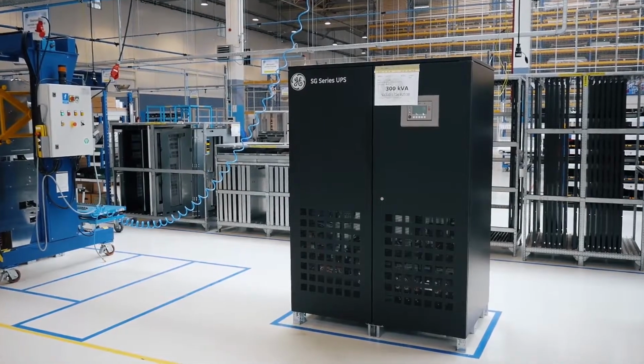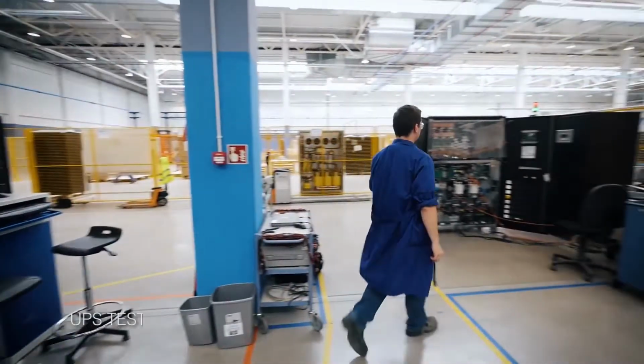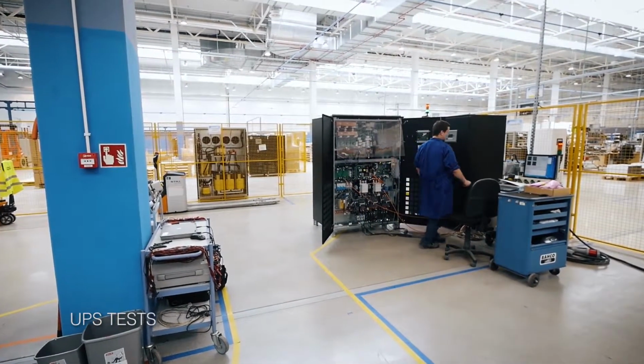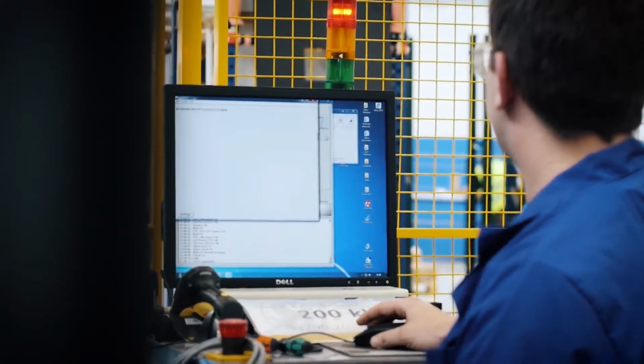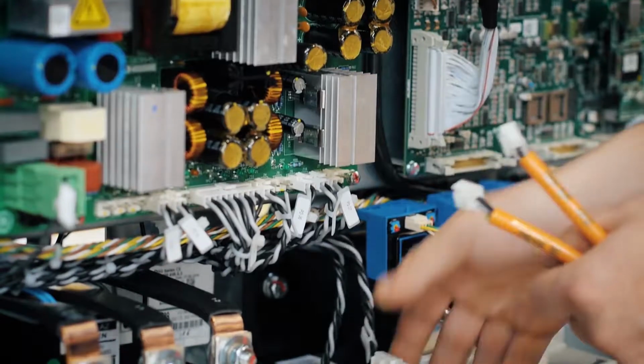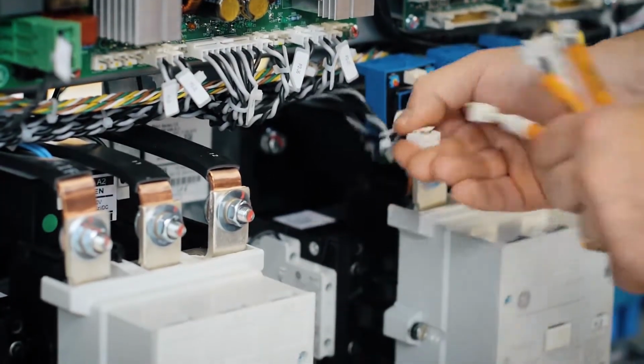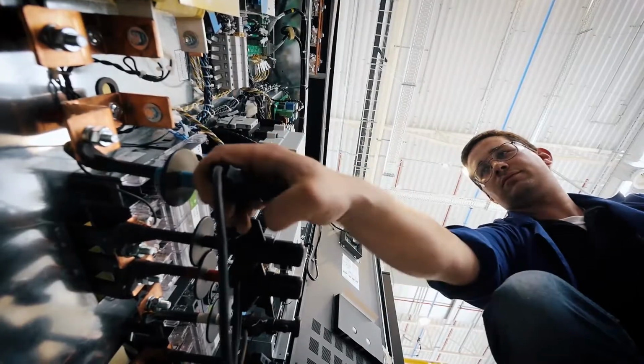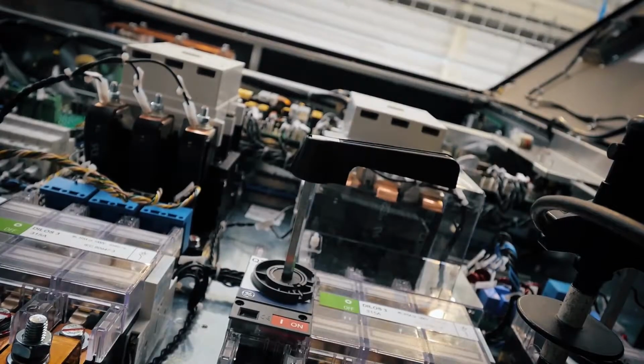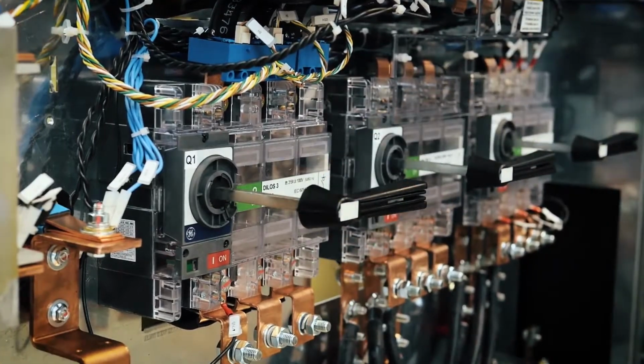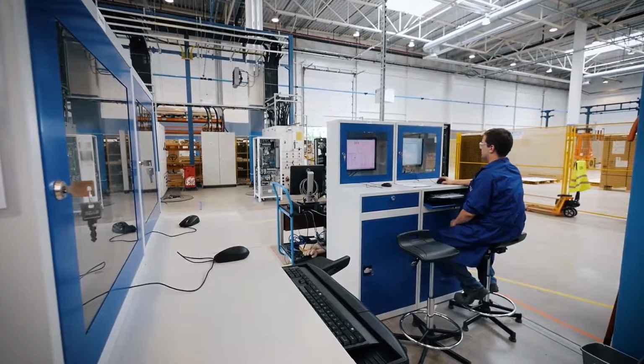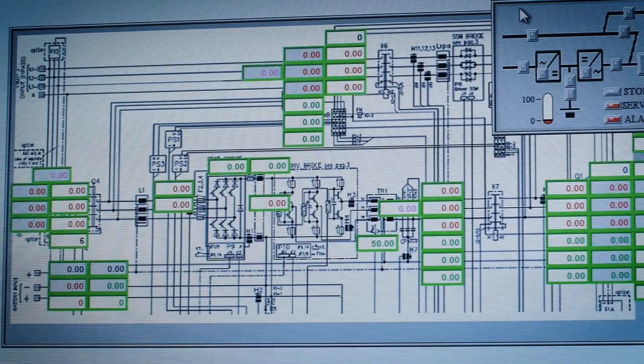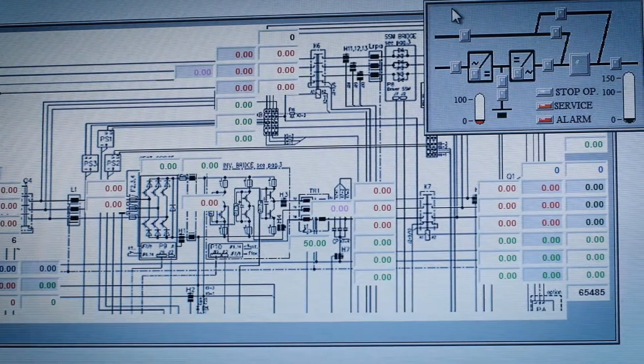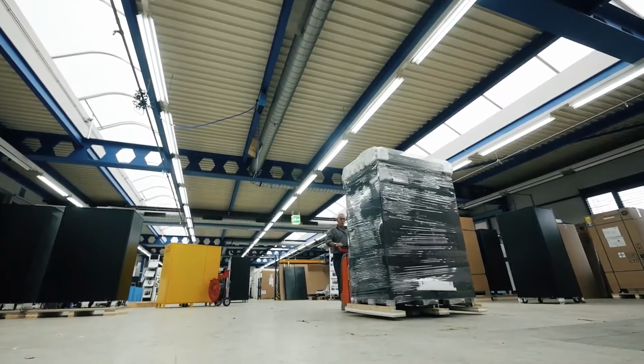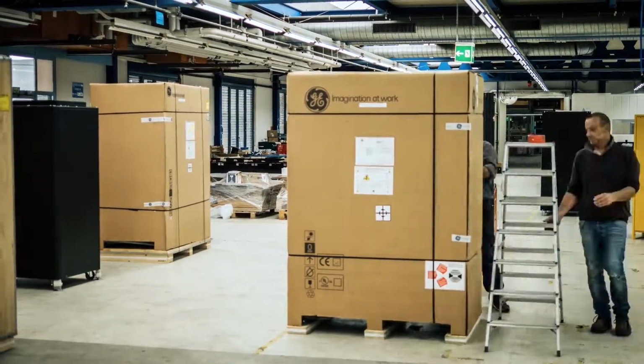The UPS is assembled. Now it needs to be checked. This is done in several stages. First, a low voltage test. A small voltage is applied to the UPS to check the connection of all joints. The UPS is then switched to the mains with standard voltage parameters to see how each separate module performs. If all modules are okay, the UPS is connected to the computer control unit. It simulates overvoltage and voltage drops in the mains. These tests last several hours. Successfully tested UPSs are sent to the warehouse or directly to the customer.